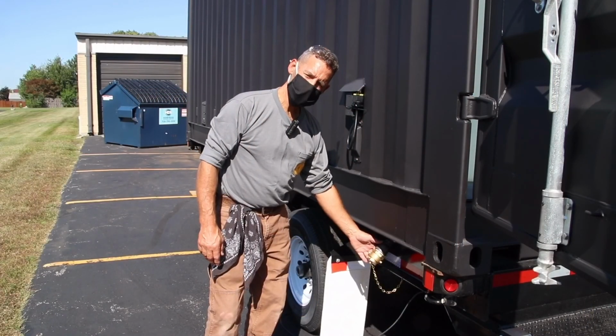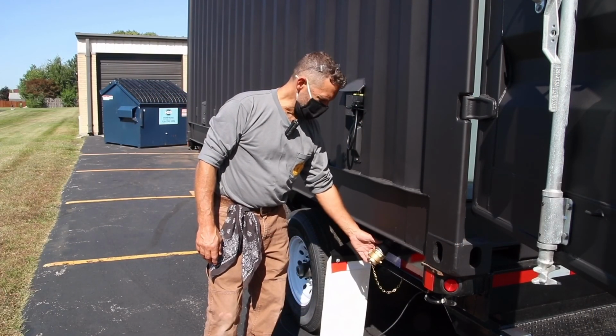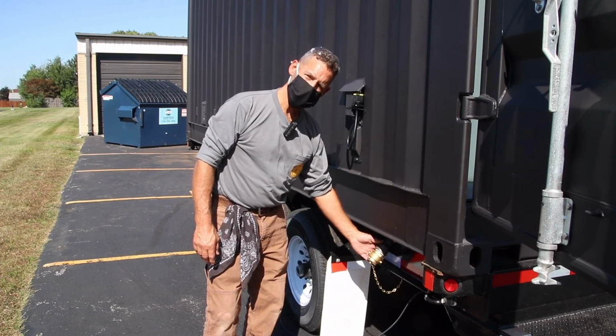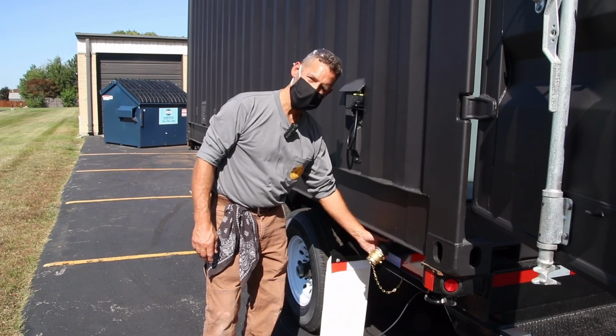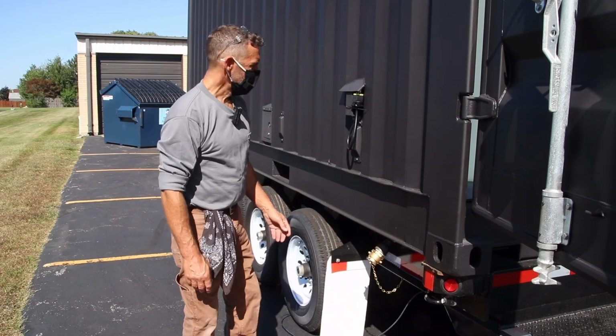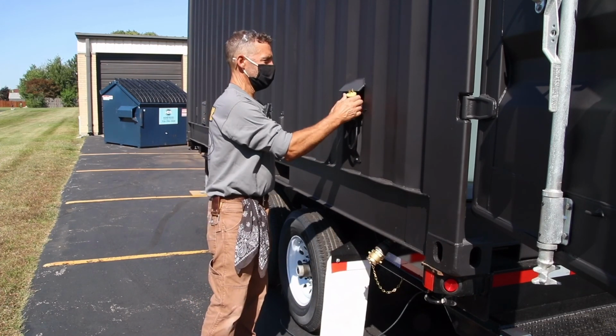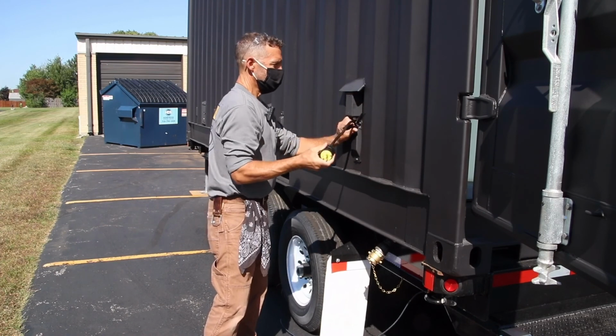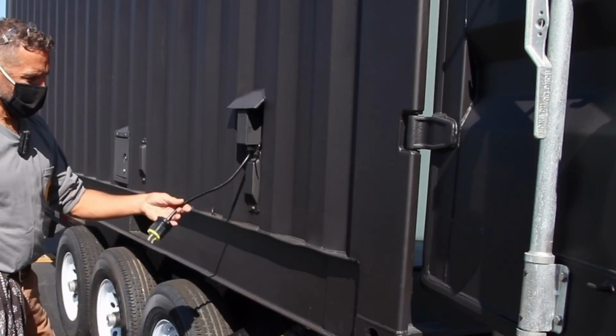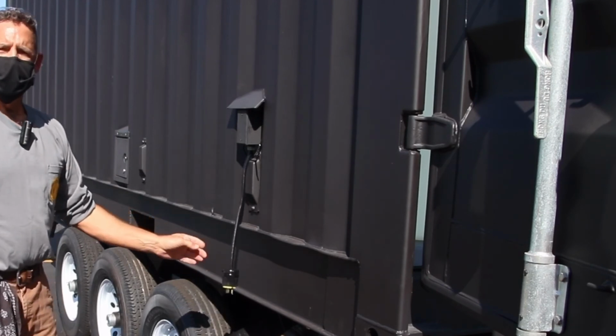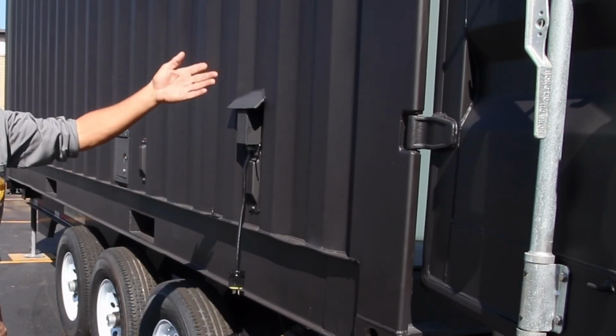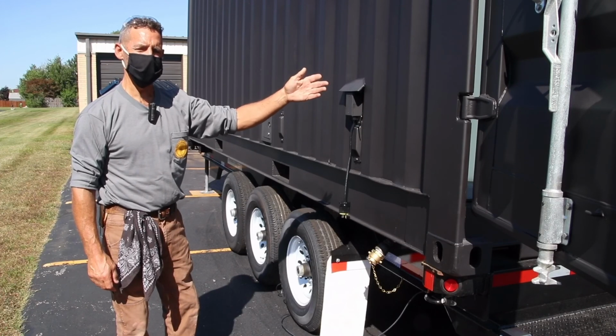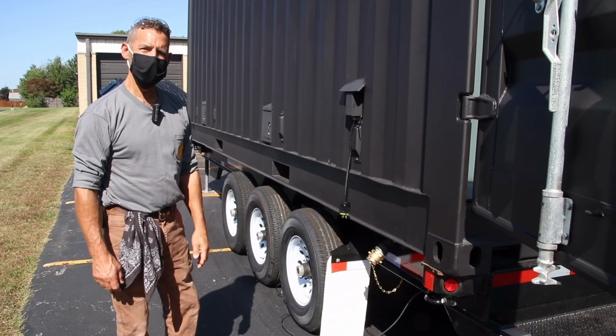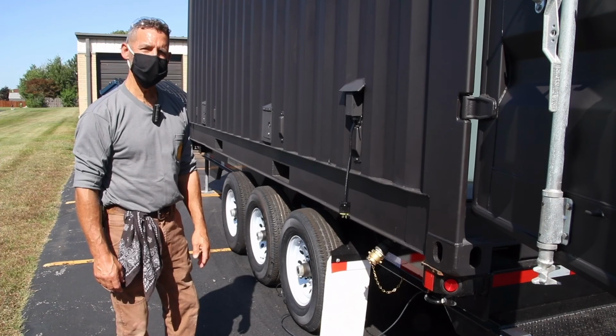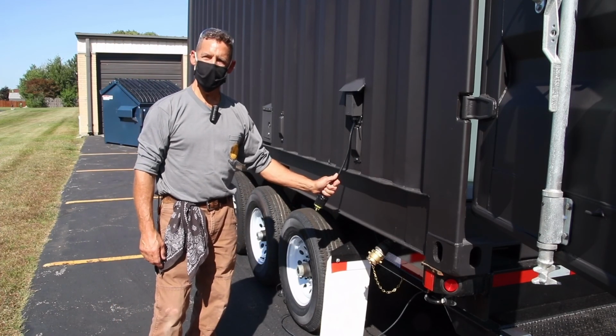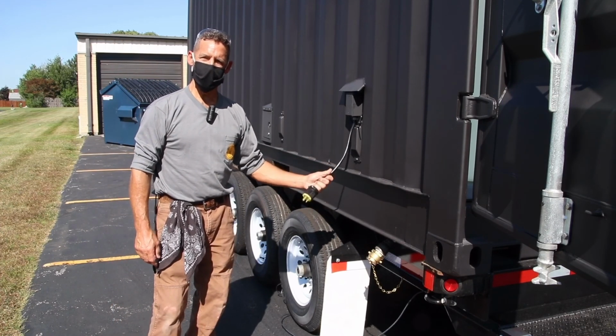The fire department that's assisting in the burn demo has the ability to hook up a 1.5 inch fire hose line directly to the piping that's mounted on the unit here. In addition to that, we have an electrical connection that will supply power through a cord set and generator to the tank and pump system and the dry pipe system air compressor. So they are all working examples of fire sprinkler systems, and they can be simulated in the field using a cord set and a generator.